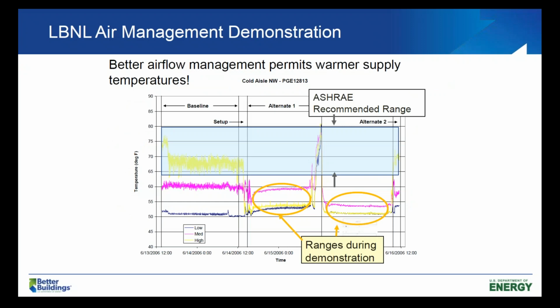So what happened when we did that cold isolation is that the three temperatures, low, medium, and high, shown on the left as the blue, pink, and yellow lines, converged and dropped in temperature to where they were below the bottom of the recommended range. What that allows one to do is raise the supply air temperature of the cooling air and still easily meet the cooling requirements. In the process of raising that, the cooling system and plant can operate more efficiently because it has a lower thermodynamic lift in order to make those temperatures. Next slide, please.